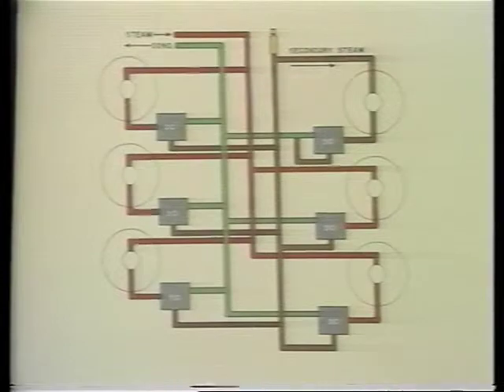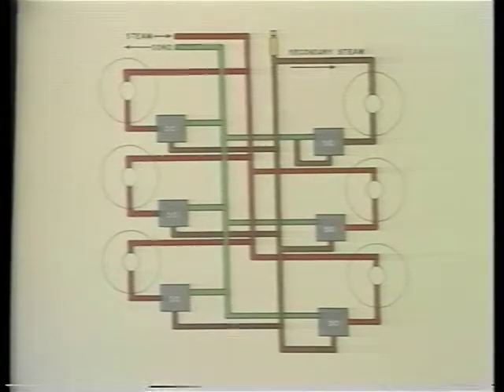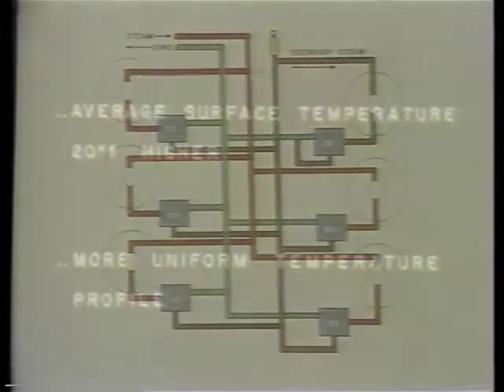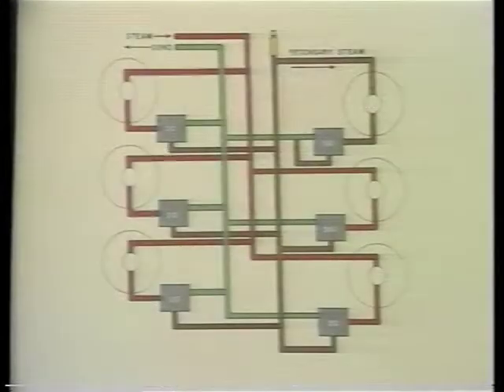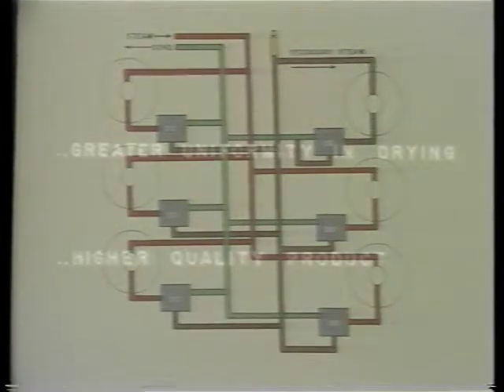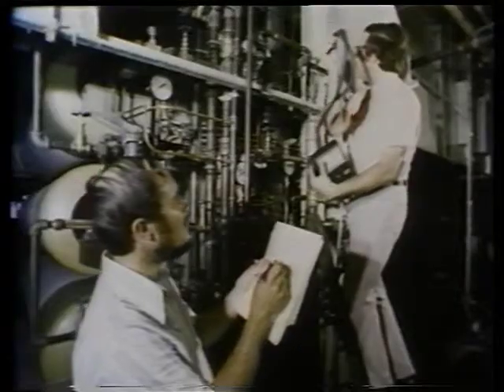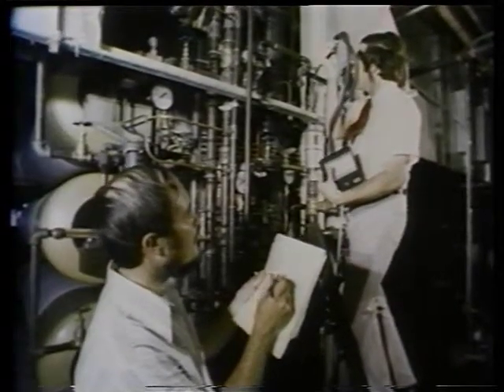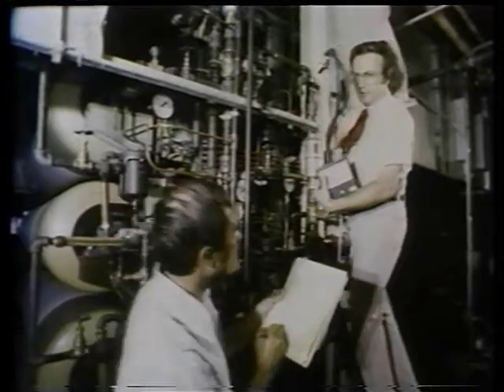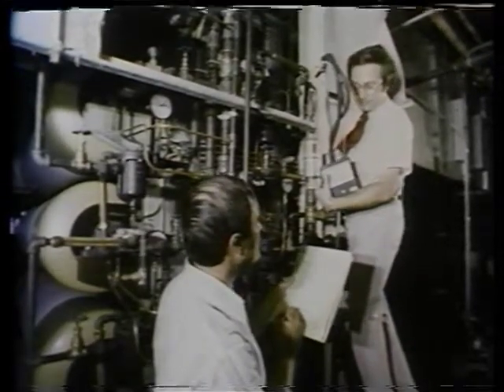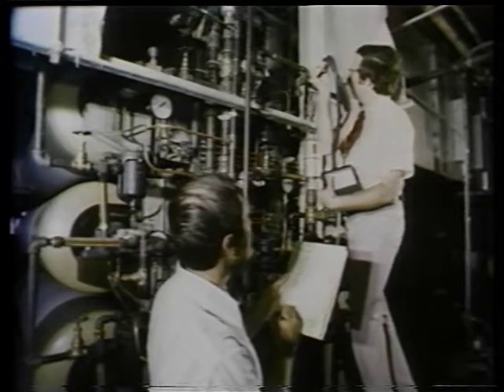In tests conducted on the same machine under identical operating conditions, cylinders drained with the HeatTech system had an average surface temperature 20 degrees Fahrenheit higher than a trap and stationary siphon system. During the same tests, the cylinders drained with the HeatTech system had a much more uniform temperature profile. This resulted in greater uniformity in drying and higher quality product. With air and condensate, which act as barriers to heat transfer, held at very low levels, the cylinder can quickly respond to changes in steam supply pressure.